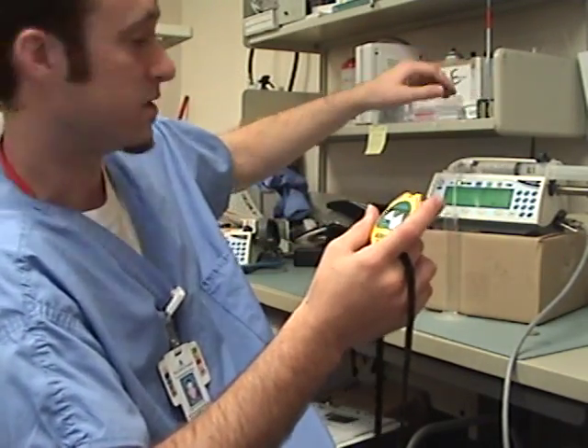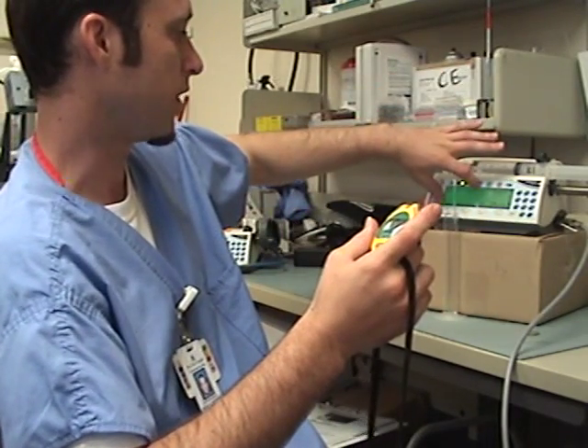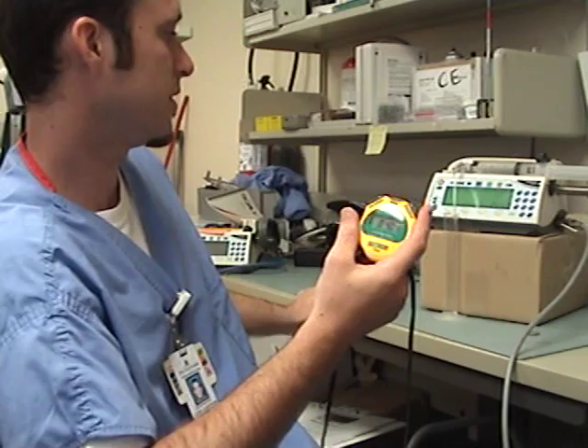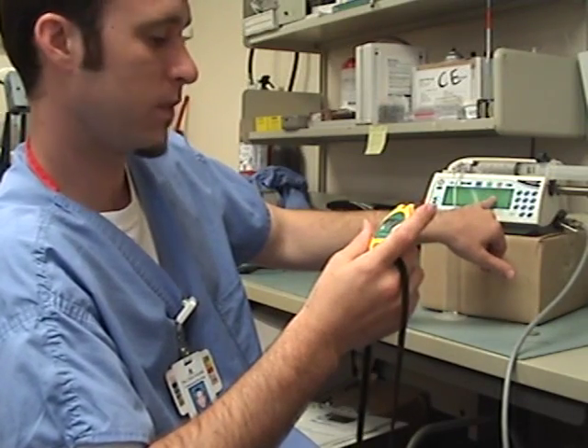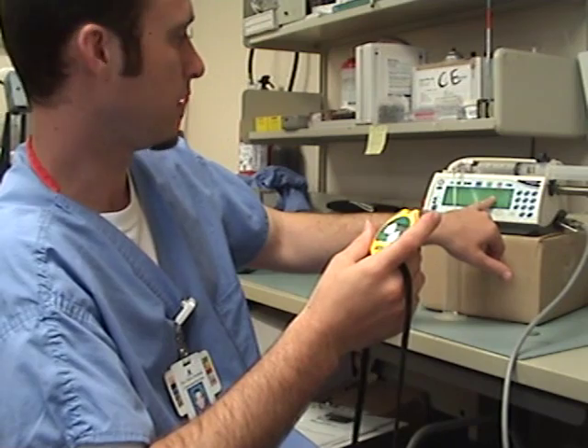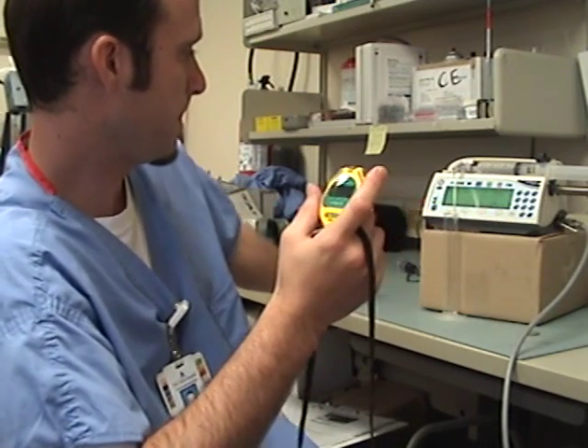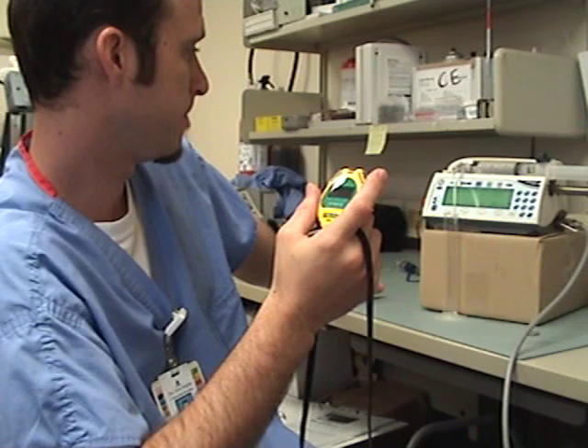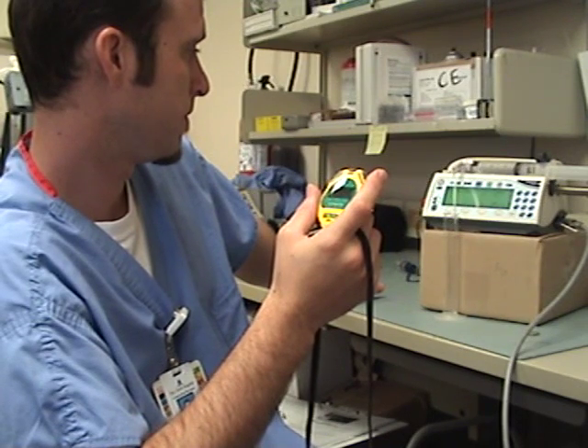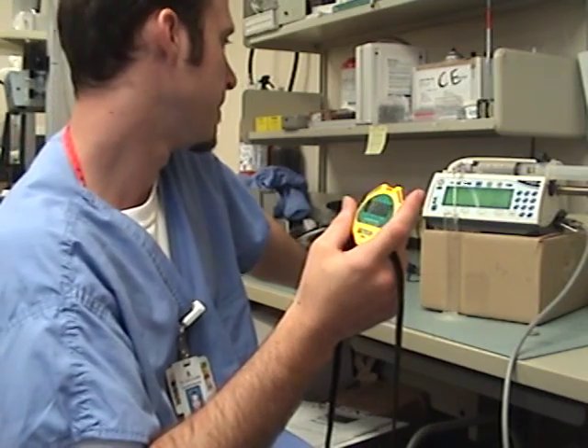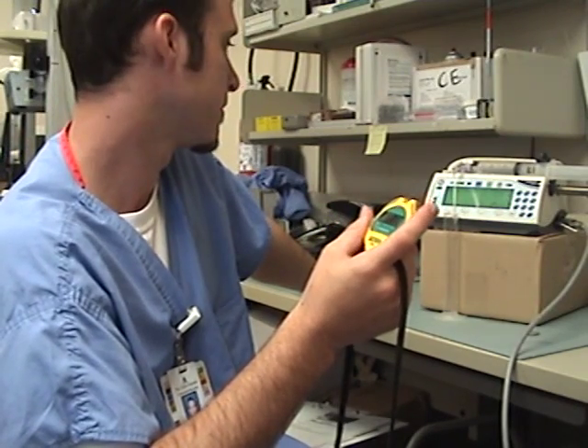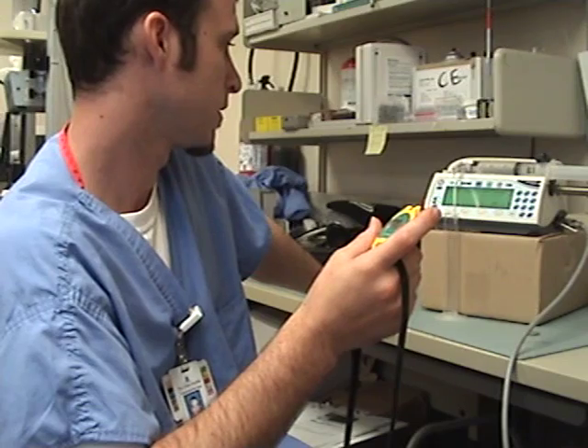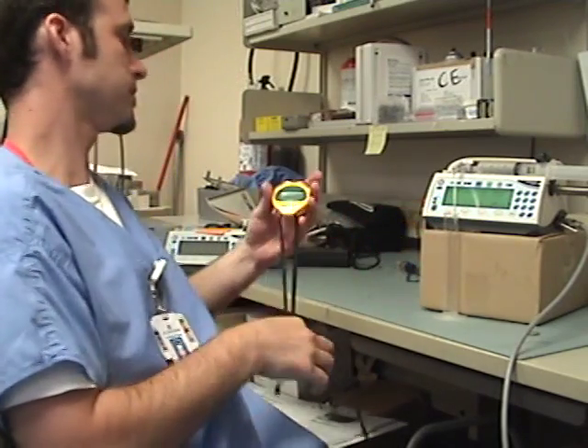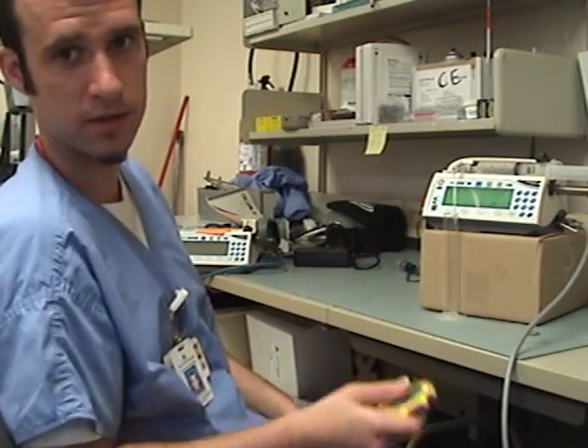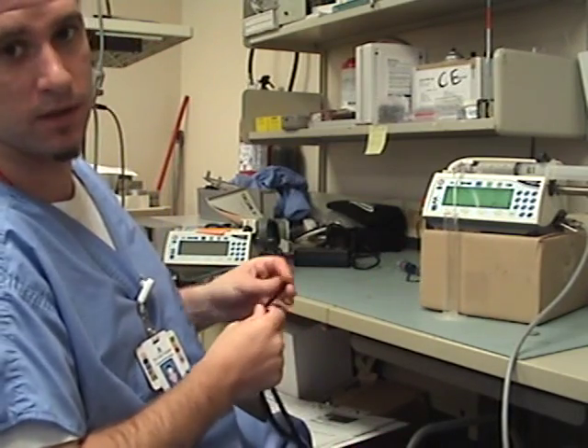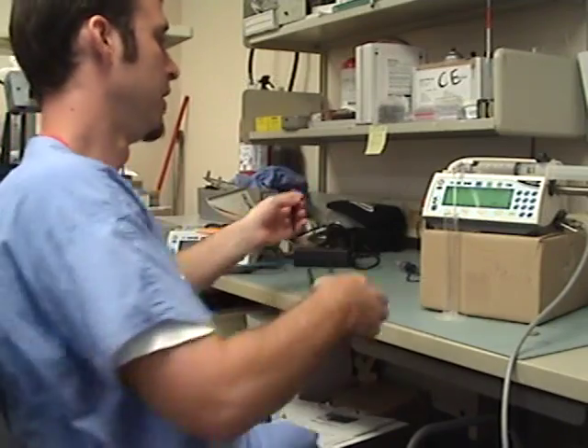On the front of the unit there's a display that shows volume to be delivered and the actual volume that has been delivered. Verify that at 1 minute you have 1 milliliter delivered. And we're right on track. Now we'll let the unit continue to run to verify that 5 milliliters actually comes out as 5 milliliters.